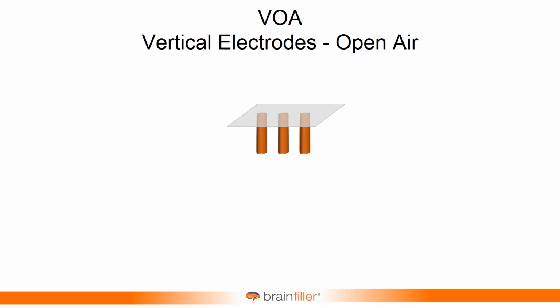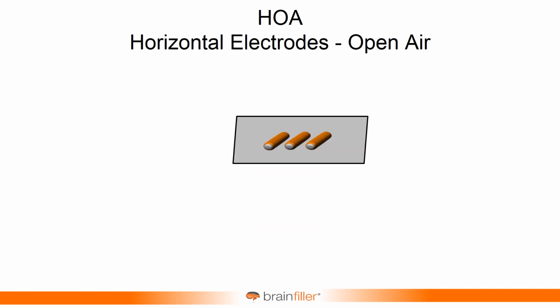And then we had the cases for open air. We have the vertical electrodes in open air. They're just suspended. That's what that little grayish thing is. And you have your trigger wire, and then you have the arc, and then the energy just shoots down. This is the same thing, or similar, I guess I should say, to what we had back in 2002. It's been refined a little bit, but it was the same electrode configuration. And then we did add another one for open air. Since we're working with horizontal electrodes, we have the horizontal electrode configuration in open air. And again, this is going to be coming right at you, but not being constrained in a box or an enclosure. It's still going to be really aggressive, but it's not going to be concentrated as much as if it was coming out of an enclosure or a box.